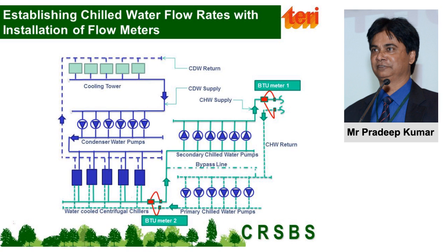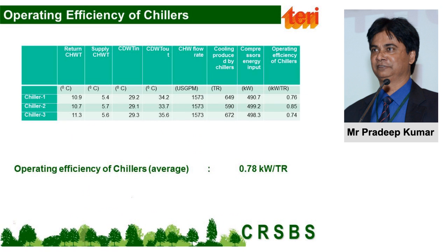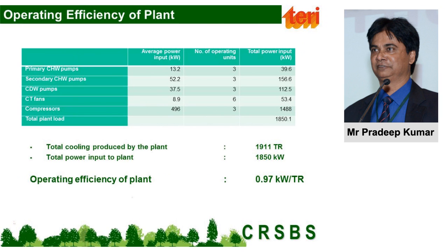So this is one of the cost-cutting measures taken by the client, because the cost of 1 BTU meter is somewhere around 2.7 lakhs or so. But this was done because it's very, very important. Once these flow meters were installed, we calculated the operating efficiency. We found that the operating efficiency of the chiller was somewhere around 0.78 as compared to the rated 0.66, and the plant somewhere around 0.97 as compared to 0.83. So it clearly demonstrated that the chillers and the plant were not operating efficiently. That makes a case to optimize it.